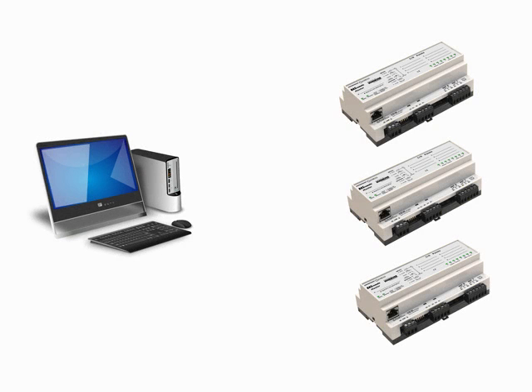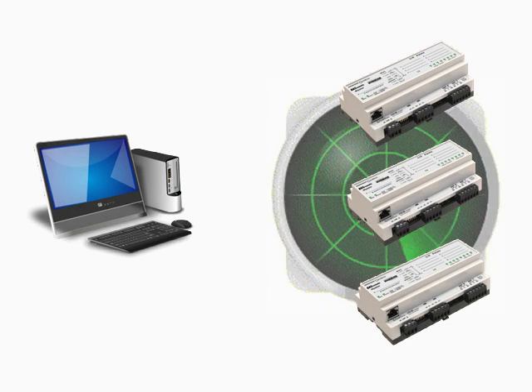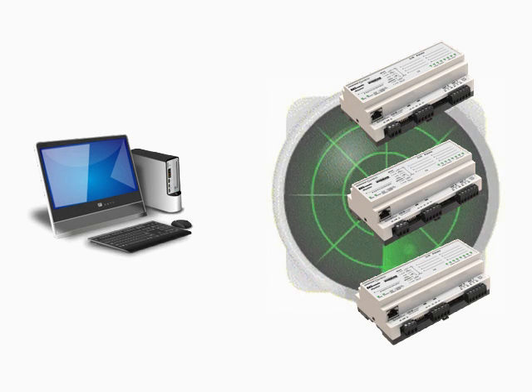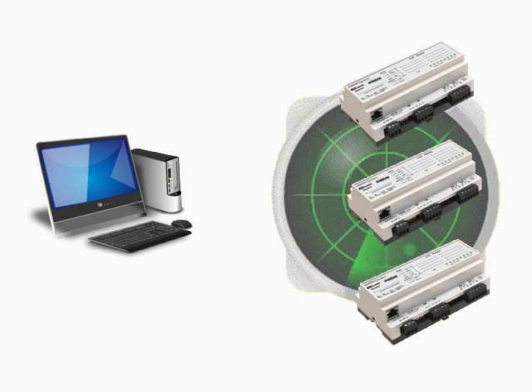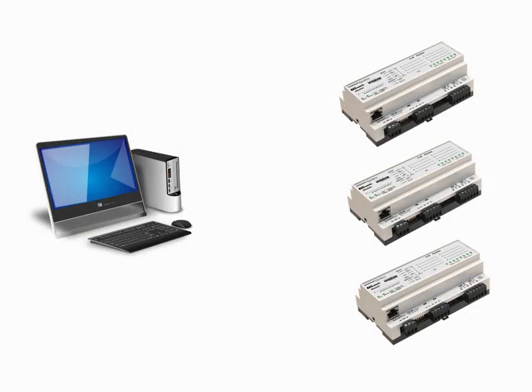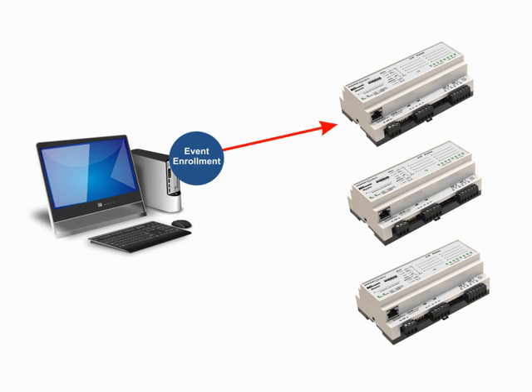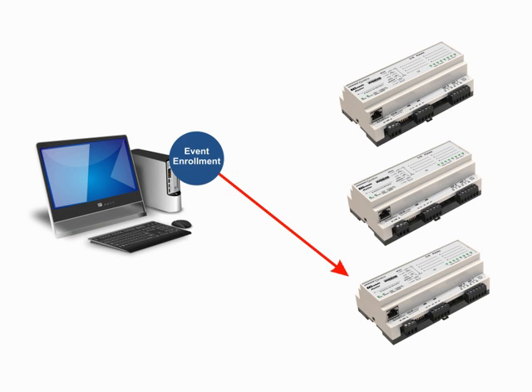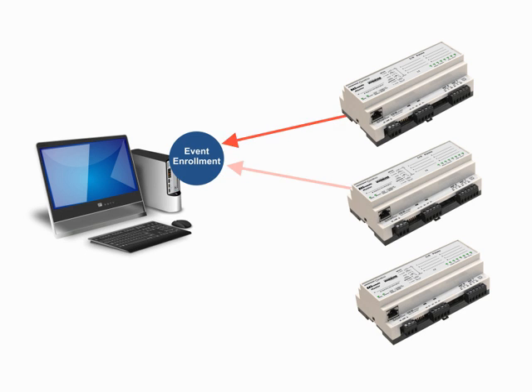There are two types of alarm reporting methods. Intrinsic reporting means that the detecting object has built-in alarm detection logic. Algorithmic reporting means that the event enrollment object is used to do the detection through constant monitoring.